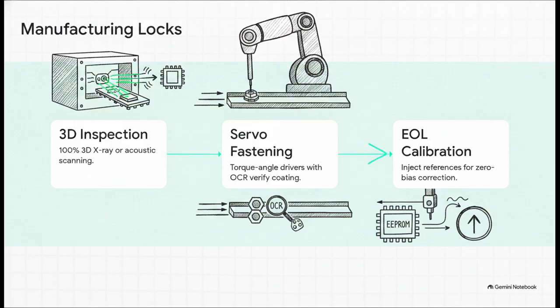Every single board gets 100% 3D X-ray or acoustic scanning. Fastening the high-voltage bus bars isn't left to humans. It uses high-precision torque angle servo screwdrivers paired with optical character recognition that guarantee the bolts have the exact right phosphate coating, keeping contact resistance under 5 milliohms. Finally, end-of-line automated calibration injects reference voltages to write perfect zero-offset correction factors right into the EEPROM.